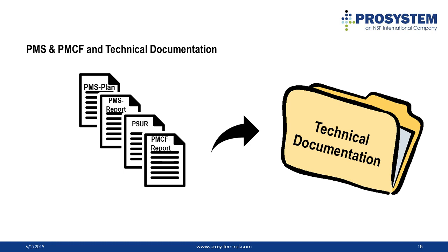The additional effort that you have to make for your technical documentation are the PMS Plan, PMS Report, and the PSUR, Periodic Safety Update Report, and the PMCF Report. In the pre-market phase, your clinical data will be evaluated in the CER. However, in the post-market phase, the PMCF report may be the main document that updates your clinical evaluation. So let's have a closer look to see what the requirements for all of these records are.